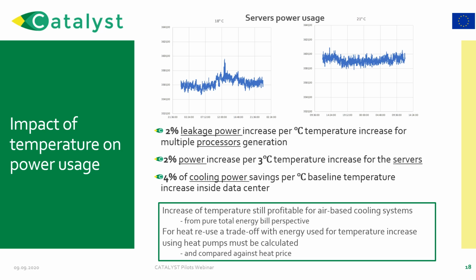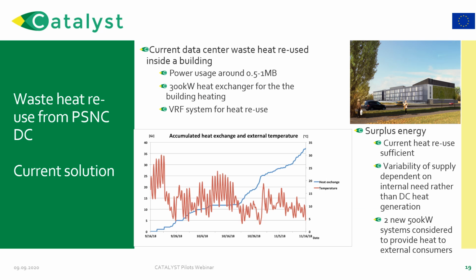Especially since the second important trial is the analysis of waste heat reuse in our data center. As I already mentioned, we use the heat from the system with power usage of up to 1 megawatt, and a 300 kilowatt heat exchanger is used for that purpose.